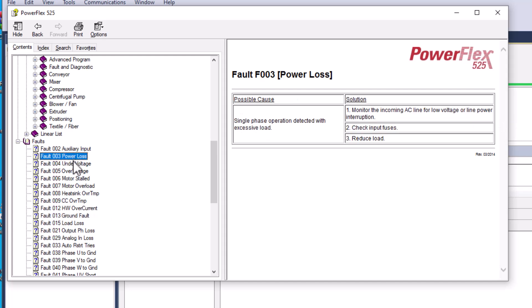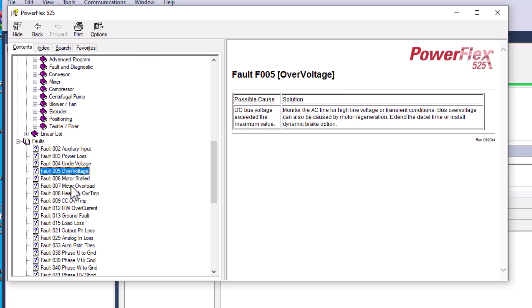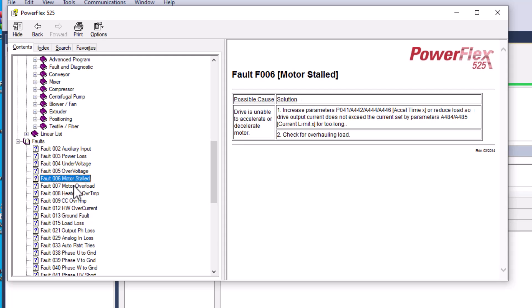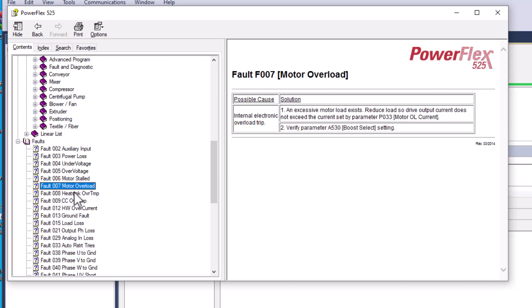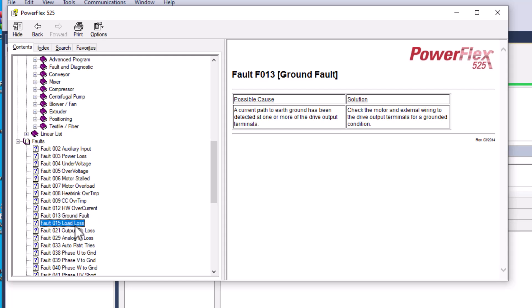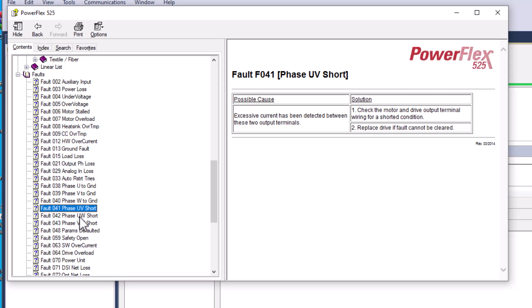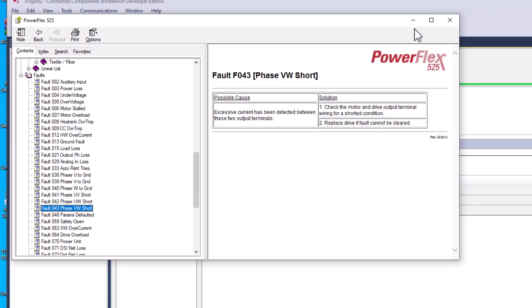You can see right here power loss, under voltage - you can see what to do with under voltage, over voltage. You monitor the voltage and it explains that you can change the decel. If you have a stall issue or motor overload, you can change a couple of things. Generally speaking, when you have a ground fault, it's going to be something done with the wiring - phase to ground, which is UVW. It will be an actual connection out in the field somewhere. It's not going to be the drive - generally speaking it's going to be in the field. I've seen that more often than not.